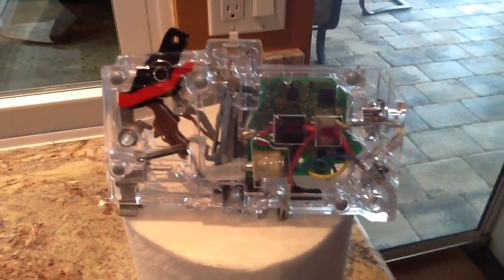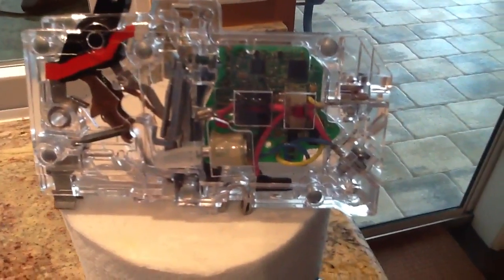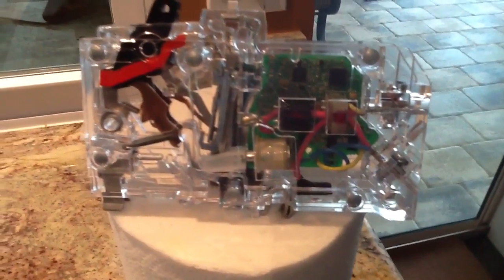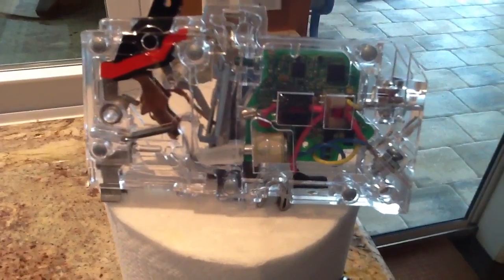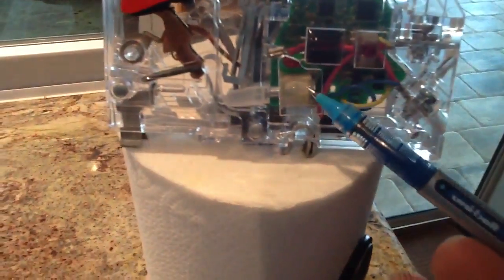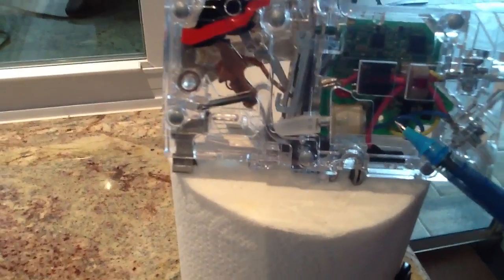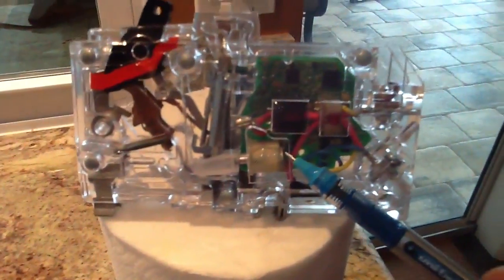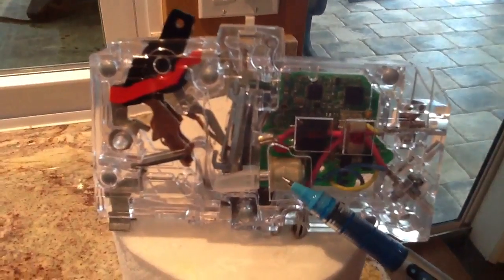What I want to talk about today is what's inside of a GFI breaker. Whether it's a receptacle or a breaker, it's going to operate the same. The first thing it does is it has a transformer right here that senses the imbalance load between the hot and neutral legs that's being monitored. This little white component is your transformer.